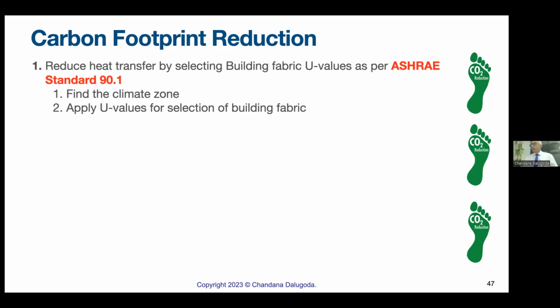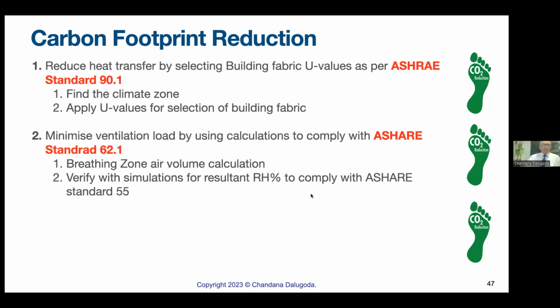Similarly, glasses, the most heat transferring element of a building, they give you the maximum U value that you should have. So we'll have to apply from the ASHRAE standard. Next, minimizing ventilation load using ASHRAE standard 62.1, and verify the simulations for resultant RH. Now we do a simulation, and we can even find what would be the resultant RH in the building.